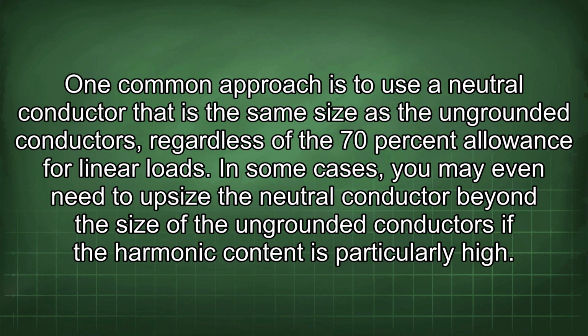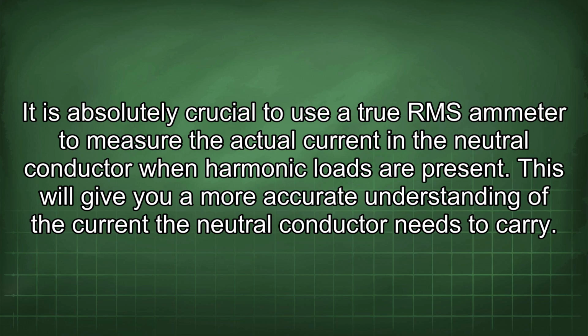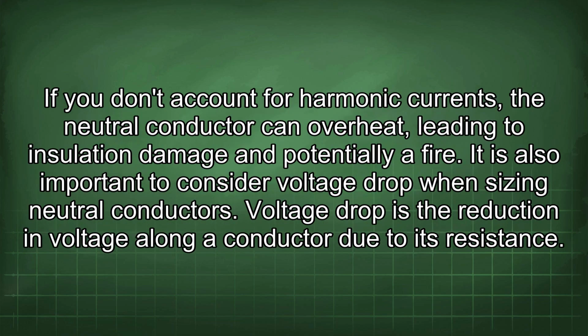In some cases, you may even need to upsize the neutral conductor beyond the size of the ungrounded conductors if the harmonic content is particularly high. It is absolutely crucial to use a true RMS ammeter to measure the actual current in the neutral conductor when harmonic loads are present. This will give you a more accurate understanding of the current the neutral conductor needs to carry. If you don't account for harmonic currents, the neutral conductor can overheat, leading to insulation damage and potentially a fire.